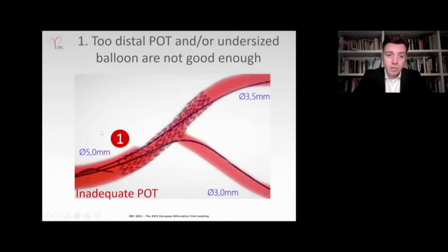What you see now here on this bench test is that the wire doesn't go straight forward into the stent lumen. It rather still can go behind the struts, and you can still have abluminal rewiring, even though you think that you have performed POT. It was not performed correctly, and it leaves the proximal part of the stent still not expanded well with a large portion of malapposition.